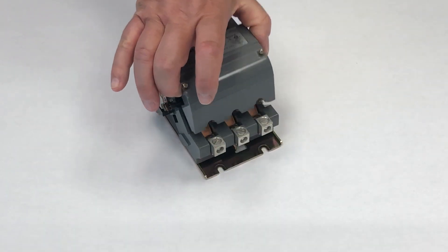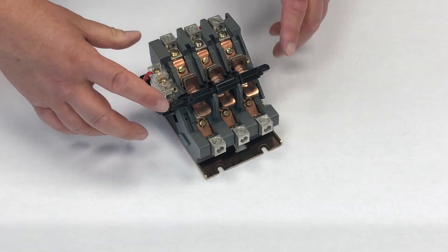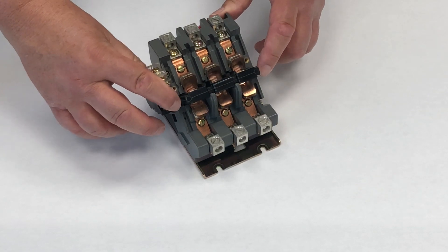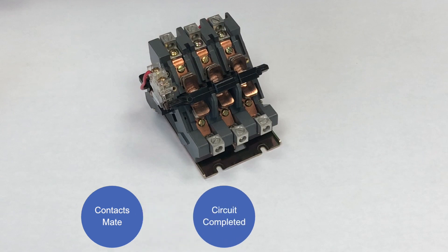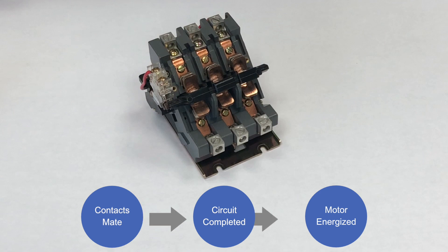We'll remove the cover to expose the contacts. When the coil becomes energized, it pushes — or in this case, magnetically pulls — a metal plate downward in the contactor. The movable contacts are attached to the plate, mounted in a holder, which then contact or mate with the stationary contacts. When they mate, the circuit is completed and will start one or a number of motors. So a contactor is simply an electrically controlled switch that completes or interrupts a circuit.